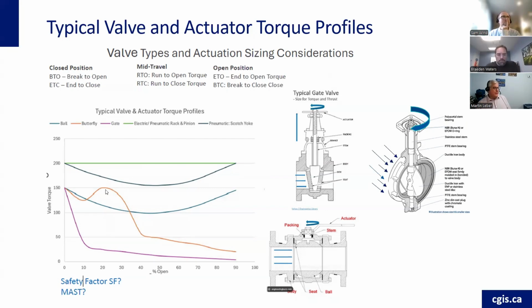So really, if it's a gate valve, you would size it based on unseating torque and put a factor of safety on it. Typically, the valve manufacturer should be providing you that information. Now, again, the valve manufacturer is going to say, well, I don't know what media you're running it through, I don't know all these things. So it comes down to experience. There are rules of thumb, such as 1.3 being a typical factor of safety that you'll often hear about, but it's really got to do with the application that it's being used in.